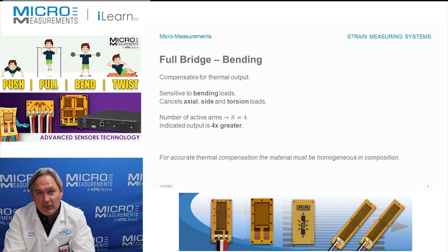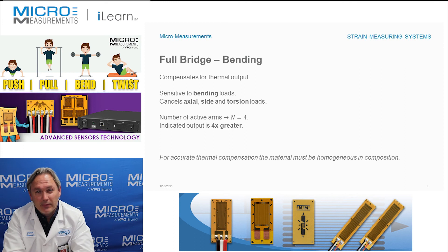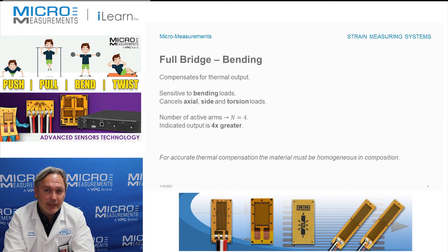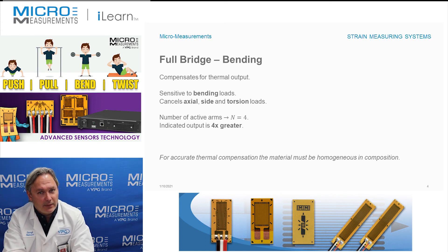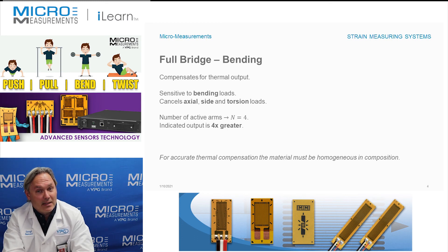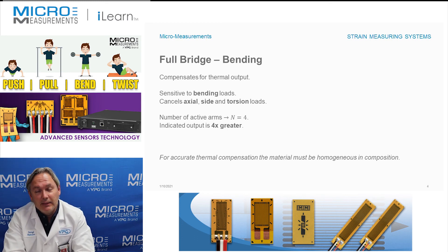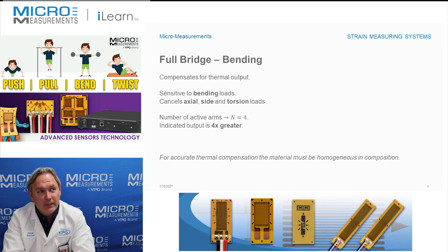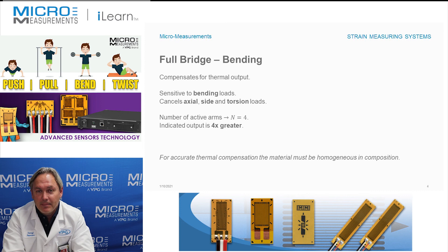The indicated output ends up being four times greater, meaning we get an electrical signal output that's four times the amount from a single strain gauge. In strain gauge measurements, it's rare that you have too much signal — most of the time it's not enough — and this is a way to increase your output by a factor of four. If you'd like to find out more about a full bending bridge, take a look at our website at www.micro-measurements.com.